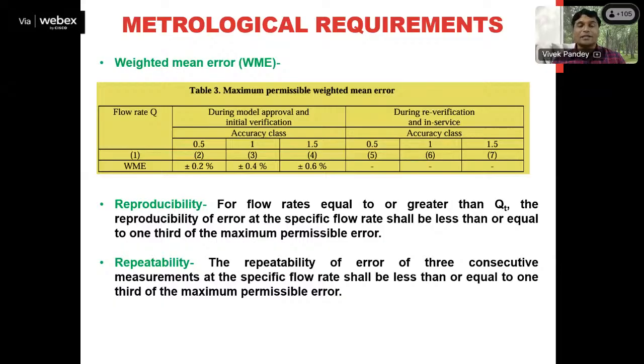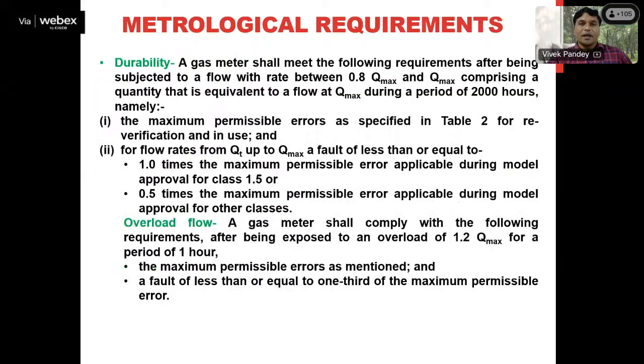So what is now the variation in its accuracy? What is the variation in the error observed in the different indications? That variation, meaning the maximum error minus the minimum error, for the different indications should again not go beyond 1/3 of the MPE specified for that gas meter. So again, if the specified MPE is say 1%, then for reproducibility, the reproducibility error should not go beyond 1/3 of 1%.